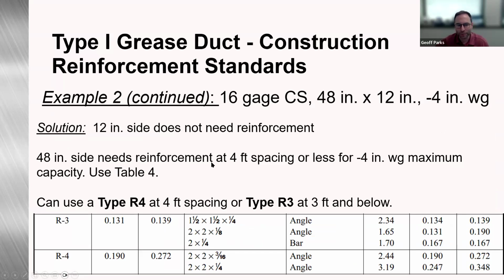So, wrapping up the whole solution here: 48 by 12, negative 4-inch water gauge, the 12-inch side doesn't need any reinforcements. On the 48-inch side, we're going to add reinforcements at 4-foot maximum spacings. And then that can be either the R4 at 4-foot or, again, an R3 at 3-foot or below.